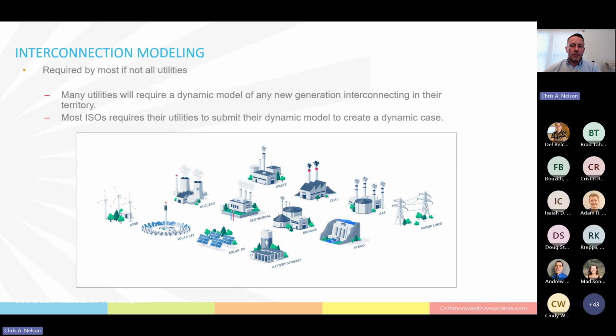And the reason they need this, usually it's not always on the utility. So the utility will collect a site dynamic file and create their system-wide model, but they have to submit their model to MISO, and it has to go up the chain a little bit. So MISO has their entire model for all of MISO that runs, and I've seen it, it takes a minute to run, but it works. And they check their whole system once they get all the data from all these little sites.